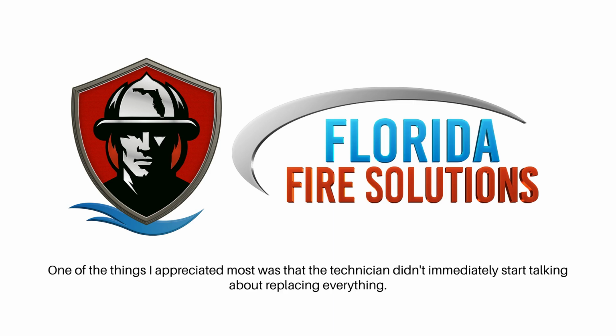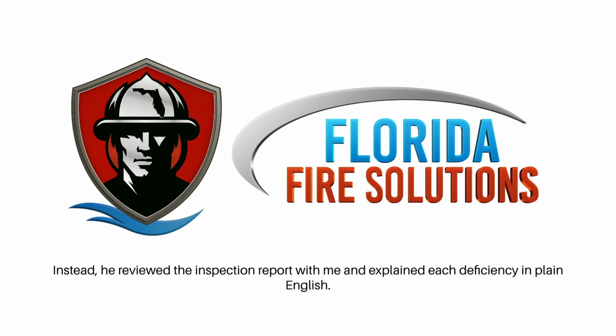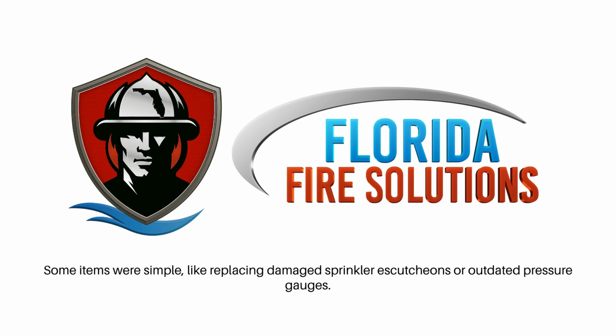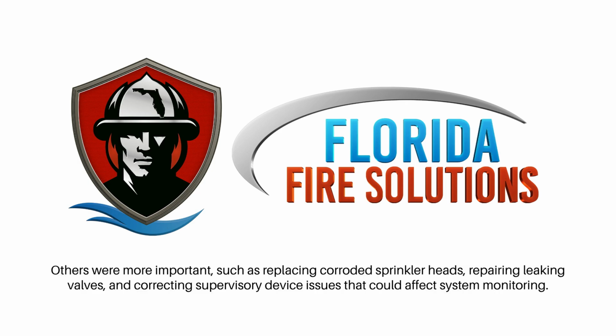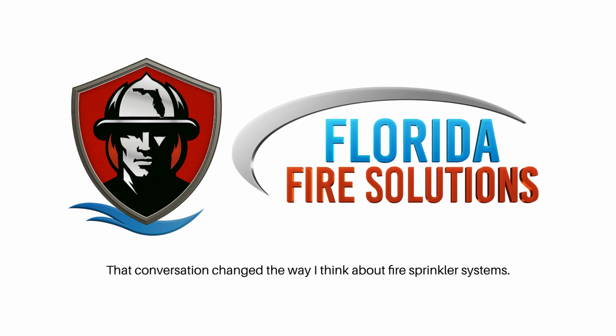One of the things I appreciated most was that the technician didn't immediately start talking about replacing everything. Instead, he reviewed the inspection report with me and explained each deficiency in plain English. Some items were simple, like replacing damaged sprinkler escutcheons or outdated pressure gauges. Others were more important, such as replacing corroded sprinkler heads, repairing leaking valves, and correcting supervisory device issues that could affect system monitoring.